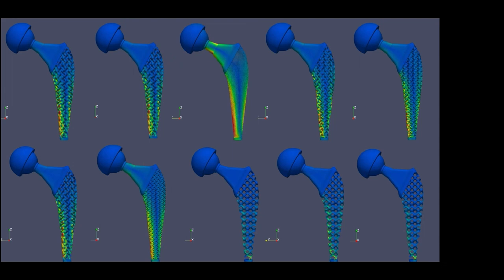Here we have a hip implant where we latticed the part integrated into the bone. We used different infill patterns, parameters, and different pore sizes, and then performed a mechanical analysis. The colorful images show the degree of stress occurring at each location on the implant. You can easily see that some lattices or parameters will probably work better than others. We have an automatic workflow of designing thousands of variants and automatically performing simulation on each one, with different load cases — a very important part of designing and optimizing an implant.